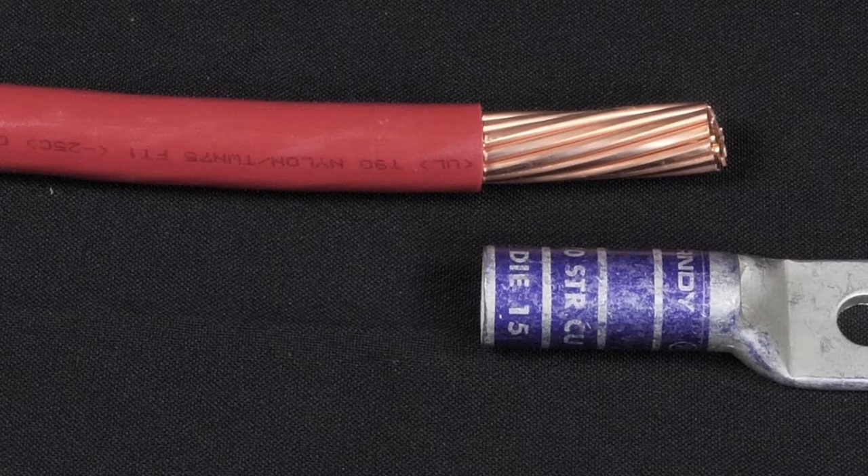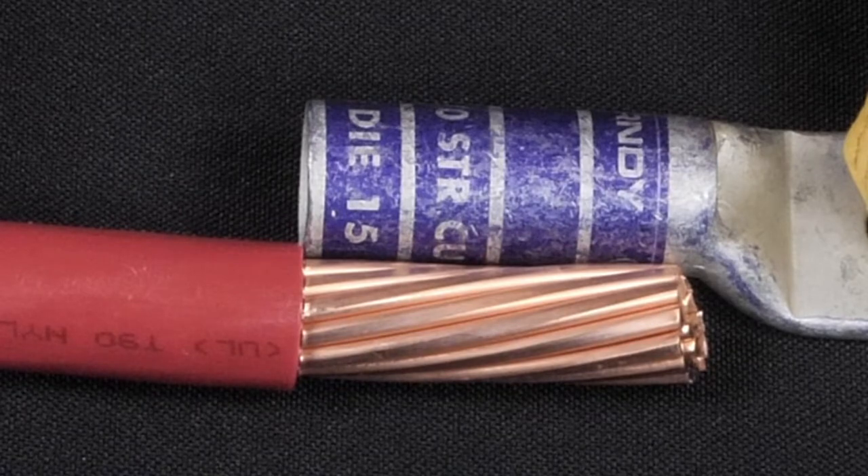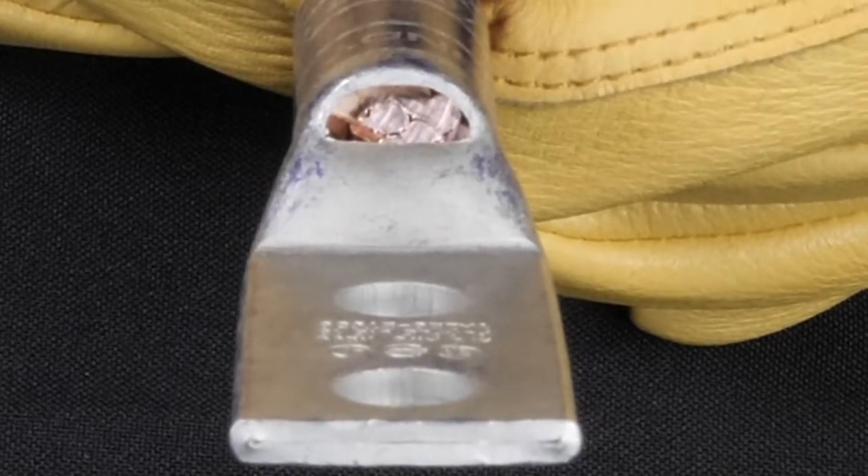Chapter 3: Proper Wire Insertion. Before making a connection, verify proper wire strip length. Hold the wire against the connector barrel so the stripped insulation is butting the barrel end. Visually verify that the bare wire extends beyond the crimp zone, as this ensures that the wire will be fully inserted into the barrel and will make full contact with the barrel when crimped.